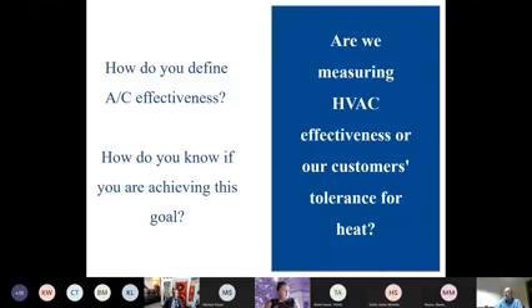Do we talk in terms of dew point? Most of the time it's gauged by our customers, our operators, our associates' complaints. So temperature and humidity are measurable parameters that define an effective HVAC system. Only after the factors of temp and humidity have been satisfied should the issue of energy savings really be considered. So are we measuring HVAC effectiveness or our customers' tolerance for heat? You've got to have clearly defined goals. I've seen a number of places where you walk in and the temperature is fine. They're actually cooled down below the 70s, but the humidity is way out of control because they're overcooling the space.